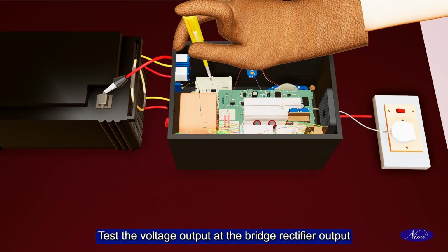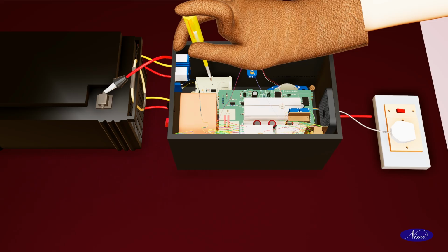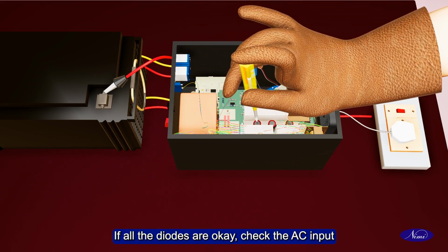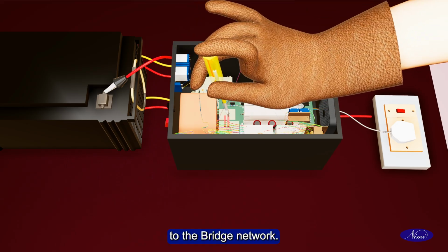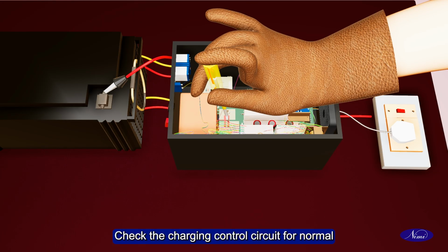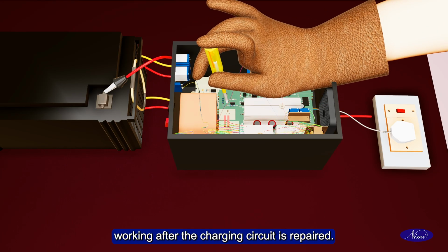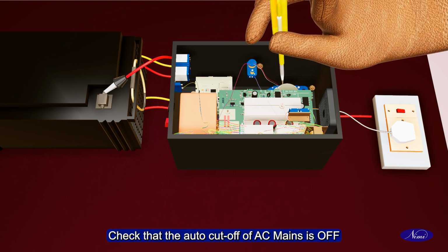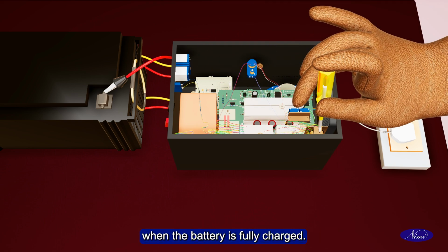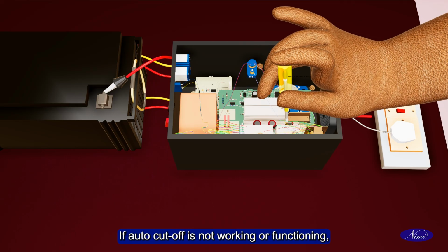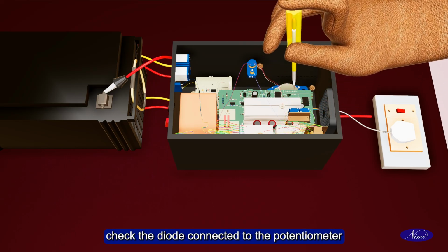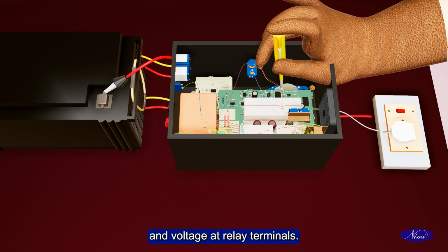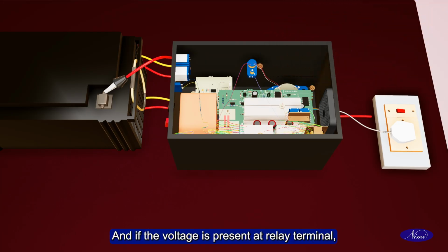Test the voltage output at the bridge rectifier output with a multimeter. Check the conditions of bridge rectifier diodes. If found defective, replace them. If all the diodes are okay, check the AC input to the bridge network. Check the charging control circuit for normal working after the charging circuit is repaired. Check the auto cutoff of AC mains is off when the battery is fully charged. If auto cutoff is not working or functioning, check the diode connected to the potentiometer and voltage at relay terminals. And if the voltage is present at relay terminal, we can conclude that the auto cutoff is okay.